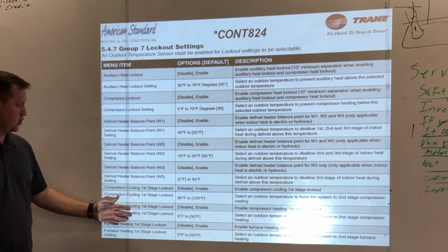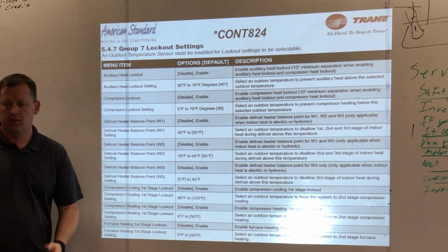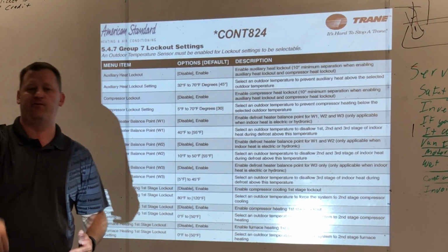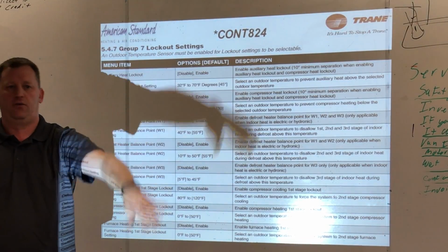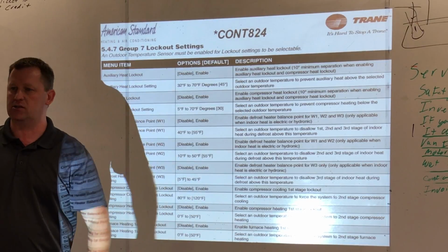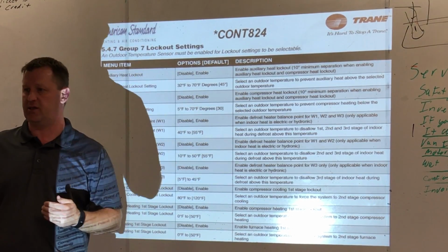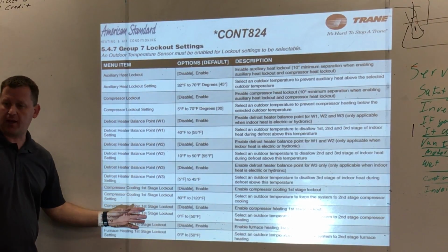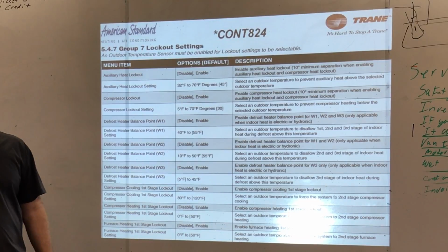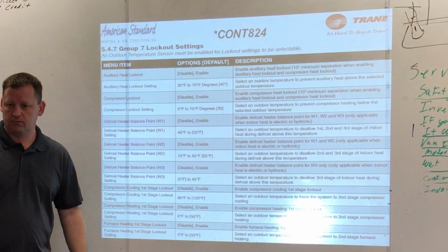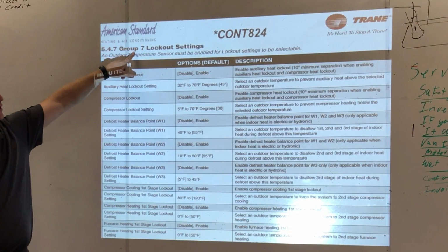Same with first stage heat pump. You know what? Just skip first stage heat pump at 30 degrees outside and go right to second stage, because we know first stage isn't going to keep up anyway. So let's go right to second stage and get it done. So we can do that. That's the only time you're really going to use these, but you could use them. And you find those in group 7 of those settings? Yep, it's in group 7.